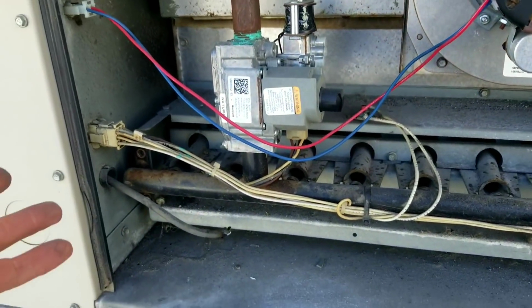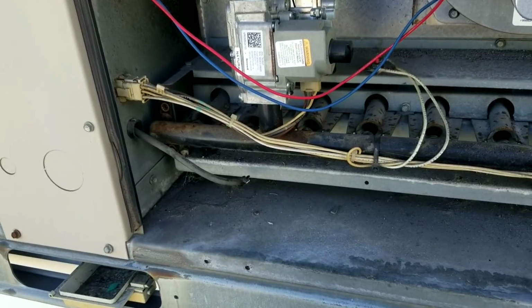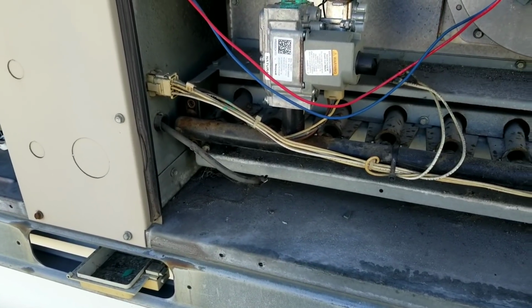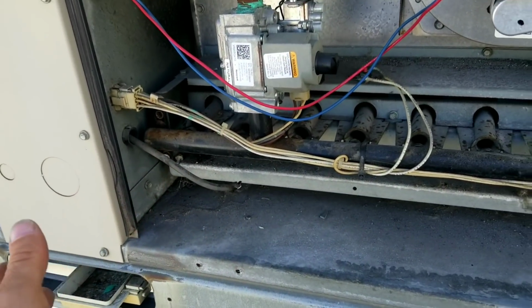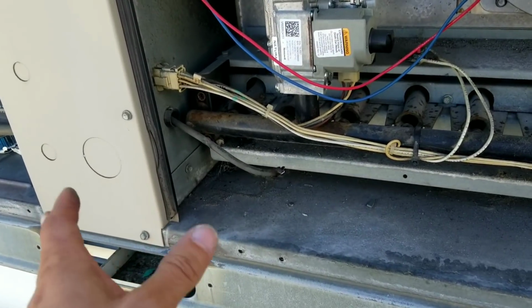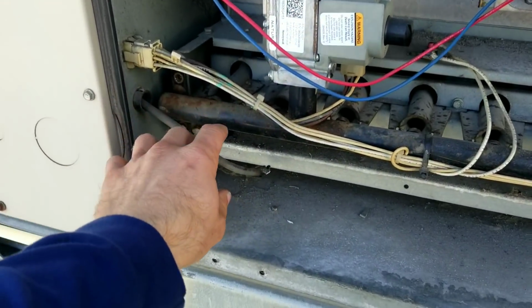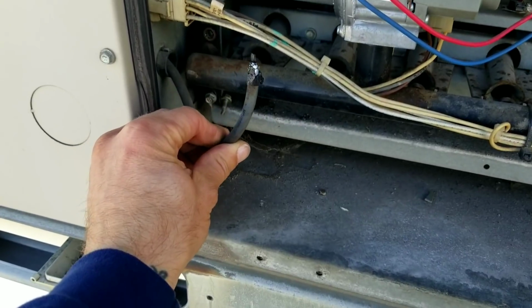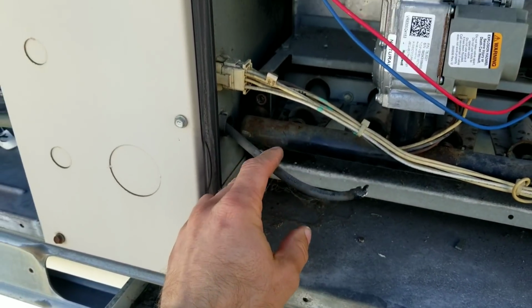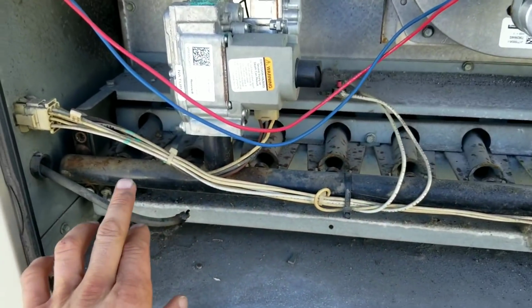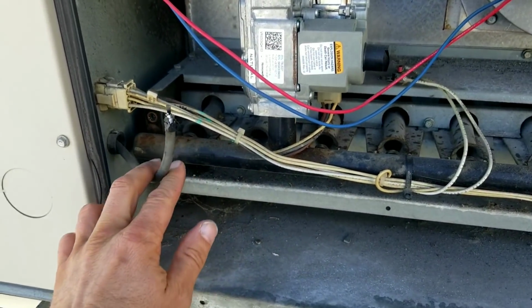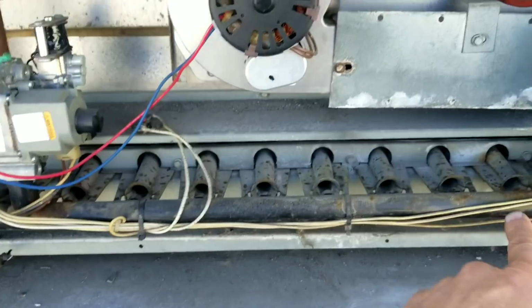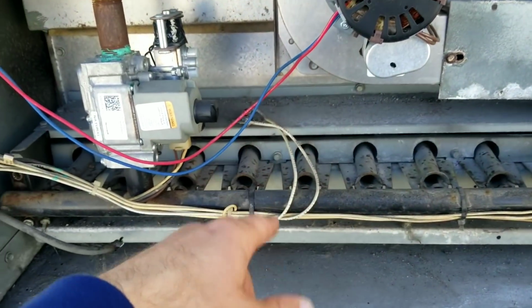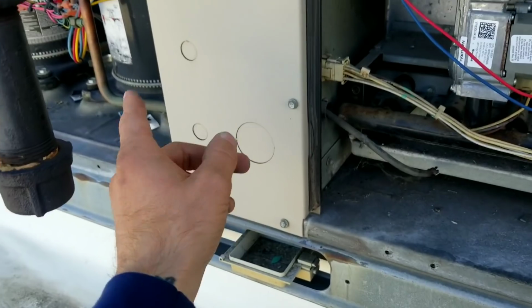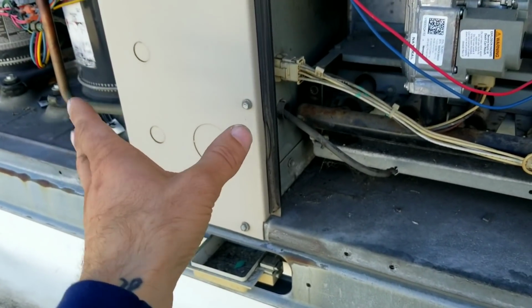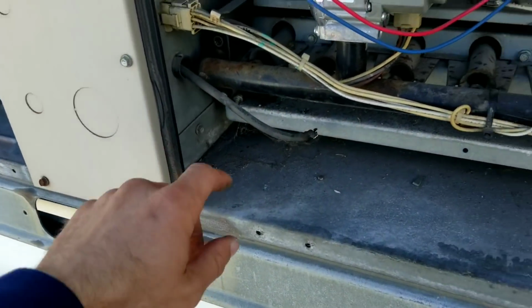I have sort of what you might call an always list, and I'm sure it varies from company to company and technician to technician. For example, if I'm going to replace this wire here, normally if everything on this unit was the same age, I would replace just about everything - spark wire, spark igniter, flame sensor, pressure switch, rollout switch, and an ignition module. But the ignition module is fairly new, so I'm just going to do the rest of it.